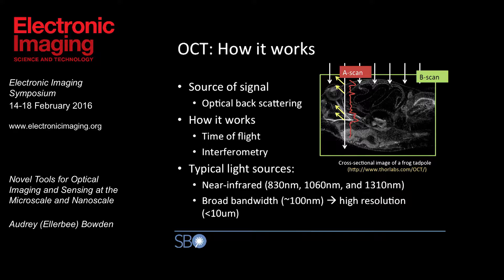If we take this A-scan and repeat the process at various locations across the sample, we achieve what we call a B-scan, which gives us our cross-sectional image. We can do this in three dimensions to achieve a three-dimensional volume. We're using a time-of-flight mechanism to measure where the interfaces are, but because light travels very fast, we can't measure time-of-flight directly, so we use interferometry. The light sources we typically use are in the infrared regime — 830 nanometers up to around 1,310 nanometers — to minimize water absorption. Another critical feature is using broadband light sources with a bandwidth of roughly 30 to 100 nanometers, which gives us our sectioning capability.